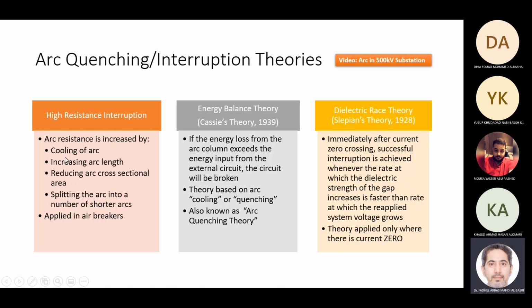This can be done by cooling the arc, so you cool the arc to extinguish it, or by increasing the arc length, so that it reduces and can be extinguished, or by splitting the arc into sections. And this is where it is applied in air circuit breakers. The arc splitter I showed you in low voltage systems is the principle here. So you split the arc into sections to make it weaker, and then you extinguish it.